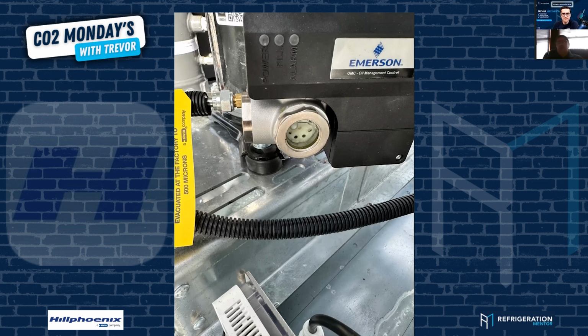But you get a call, you had an oil loss, you get out there, the compressor's running. The reason is that this sensor will actually try 5 times to fill before it locks out. So it could have taken anywhere from 2 to 3 times or 5 times to fill, but it did fill. You need to look at it. Things you need to look at.